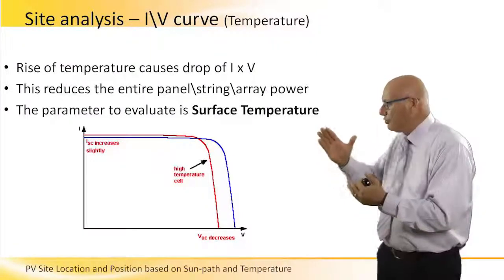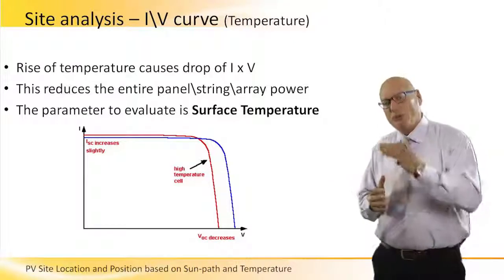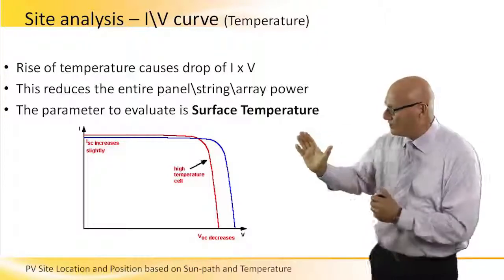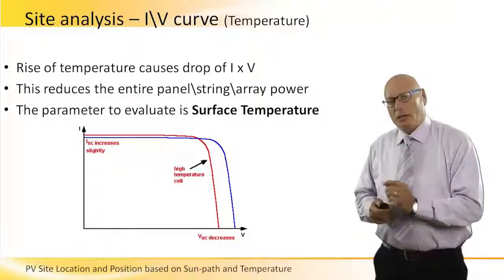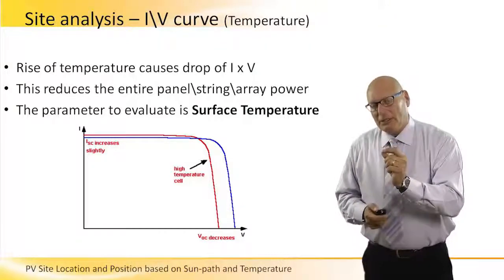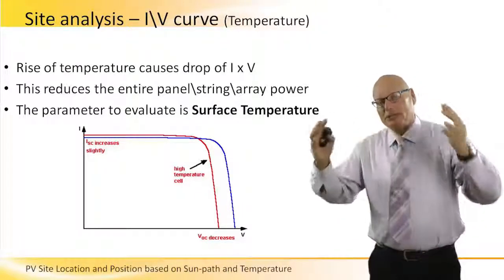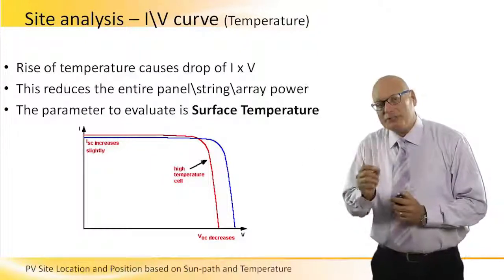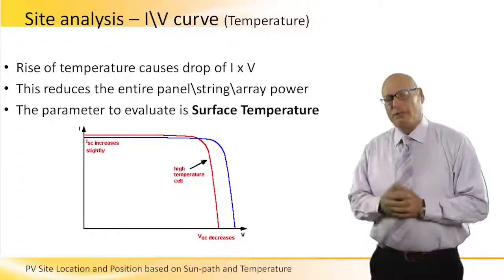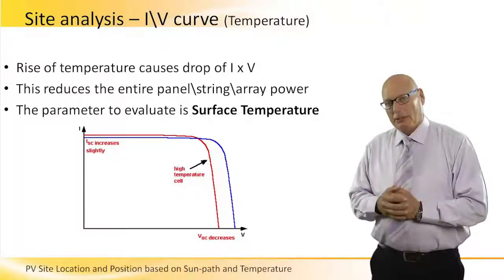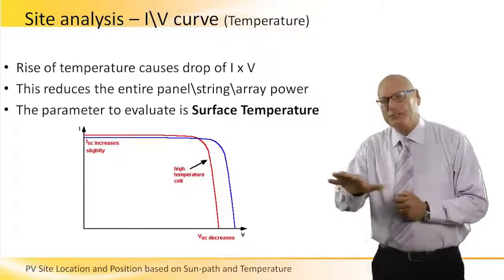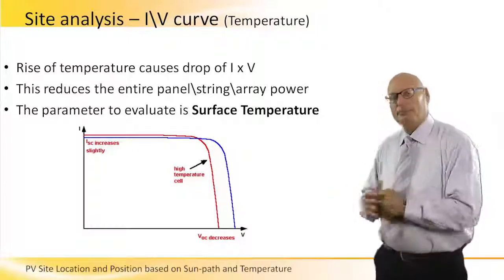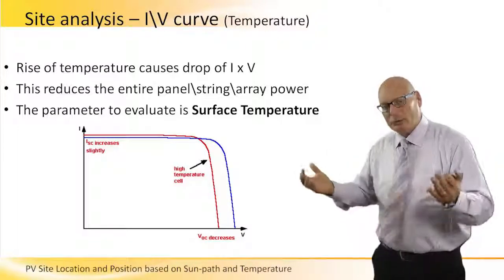Ideally, we would like to push it to the right so that both the current and the voltage are at their maximum, and therefore the power will be at maximum. But the temperature brings it left. What we are interested in is not only the surrounding temperature or environmental temperature — we are most interested in the surface temperature of the panel. The surface temperature of the panel can get to 55 or 60 degrees if the environmental temperature in the area is only 25 or 30 degrees.